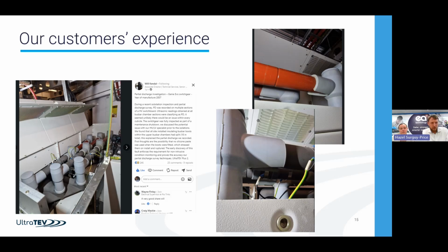People would have initially looked at that and said, this is everywhere, there's some sort of background noise. But the classifiers built into the kit now say, no, this is actually PD, and the ability to listen to stuff live rather than just look at a number on the screen or an initial light colour gave confidence to take the outage and show that actually every single boot on the bus bar in this instance has cracked. So there's a genuine issue there that once it's corrected, the levels dropped.